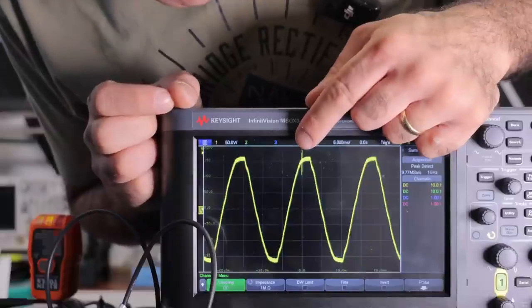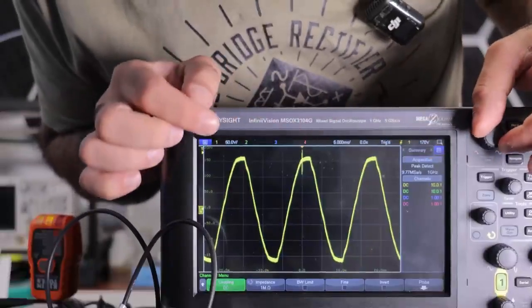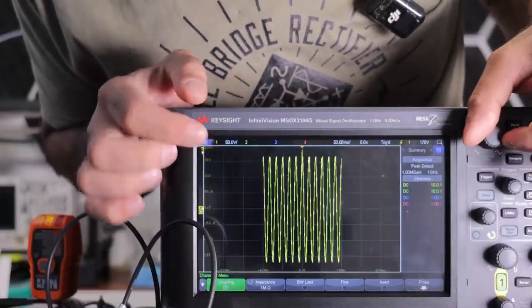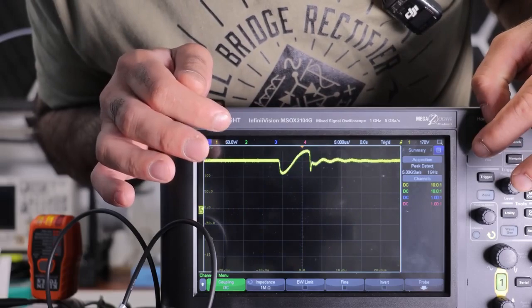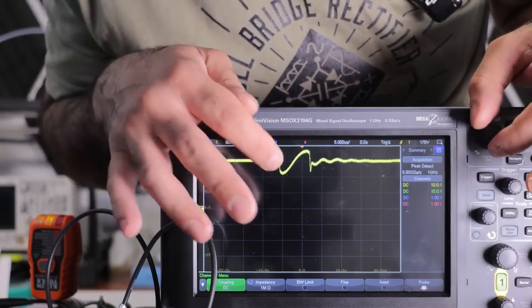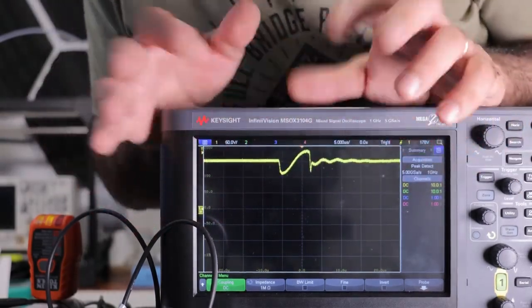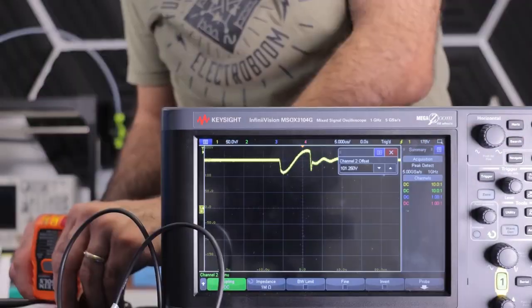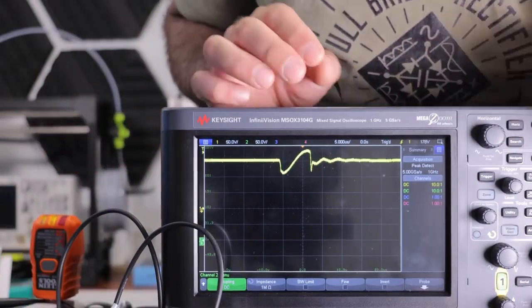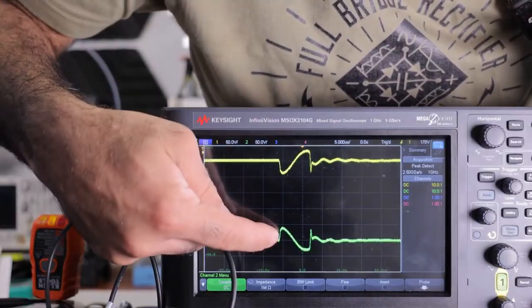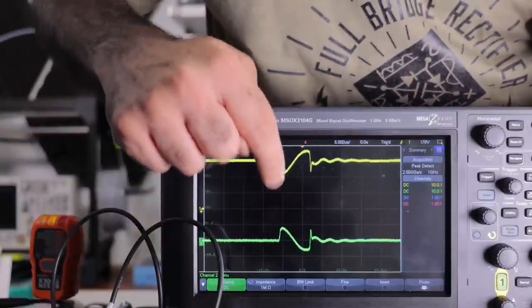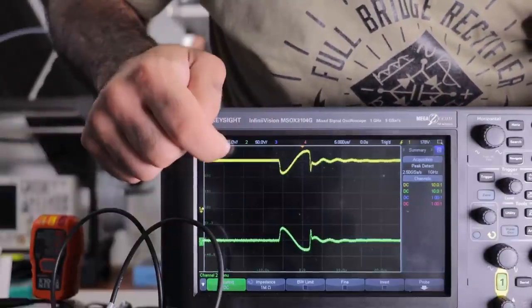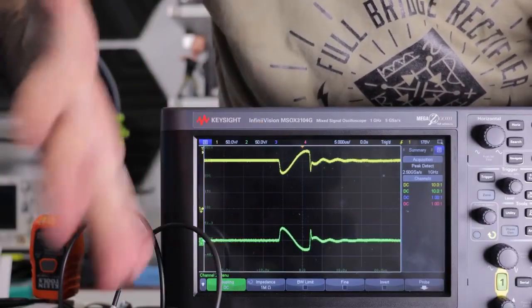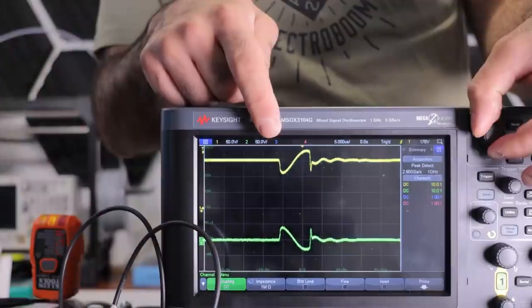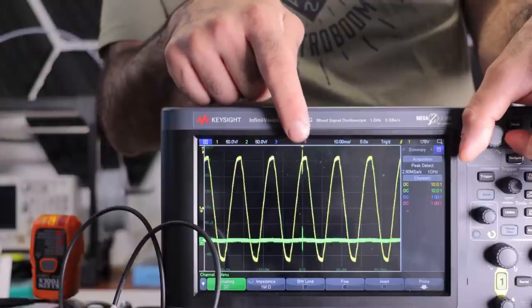It seems like there's a pulse happening on some of the peaks, every 7 to 8 peaks, around 7 to 10 microseconds wide, which translates to somewhere around 100 to 150 kilohertz. If we probe the neutral line as well, you'll see the signal is there but reversed. The peak of the signal is around 45 volts, or 90 volts combined. That's a huge signal, yeah, and it happens right on the positive peak only.